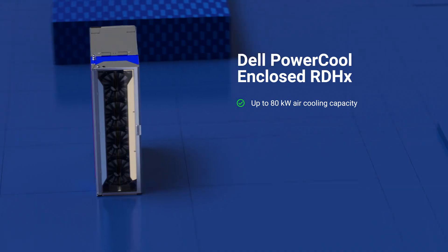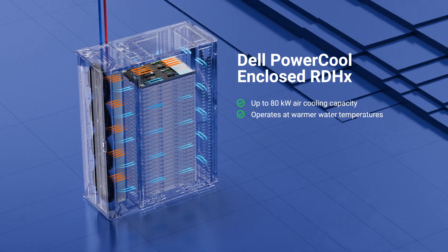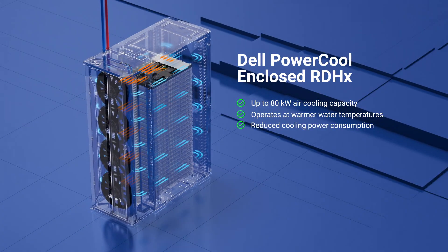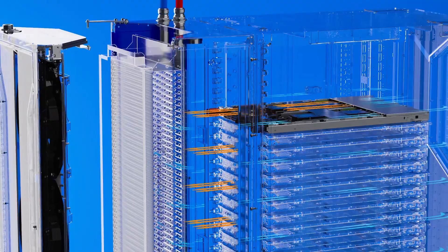By completely enclosing rack airflow and operating at warmer water temperatures between 32 and 36 degrees Celsius, the industry-first enclosed rear-door heat exchanger significantly reduces cooling power consumption compared to currently available solutions.